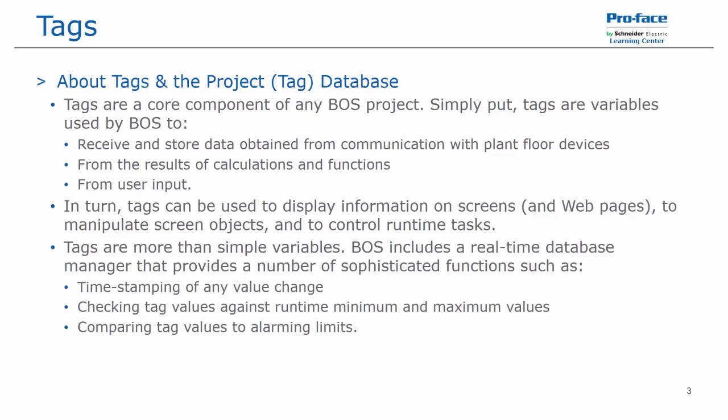But the tags are more than simple variables. The tag database or the project database in the Blue Open Studio application is a real-time manager for the tags that provides several additional functions, such as storing the timestamp of a tag when its value changes, checking the values of the tags between a runtime minimum and maximum value that a user can define in development but also during runtime, and also comparing the tag values to alarm limits.